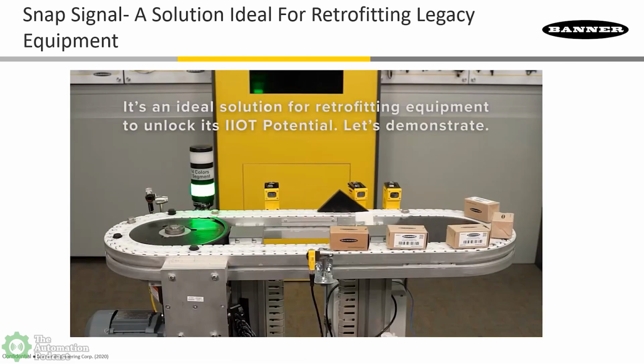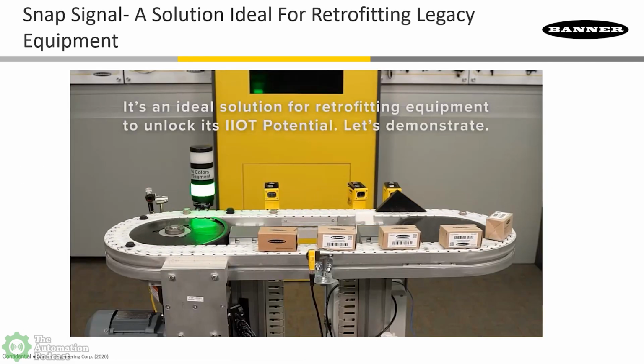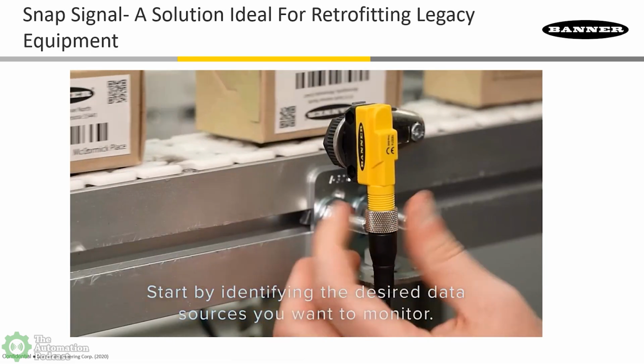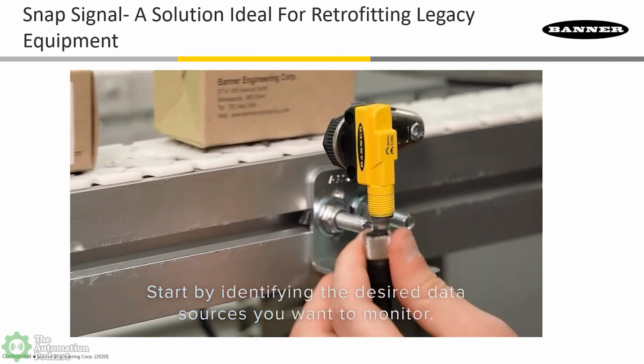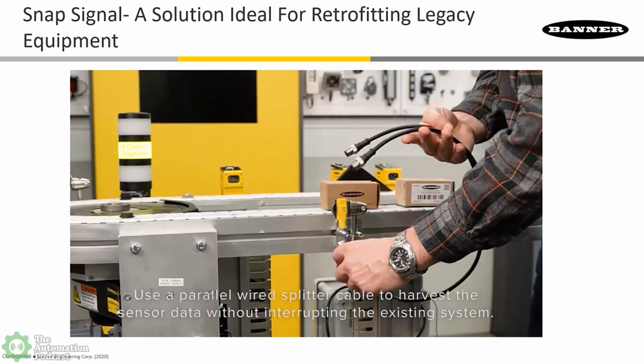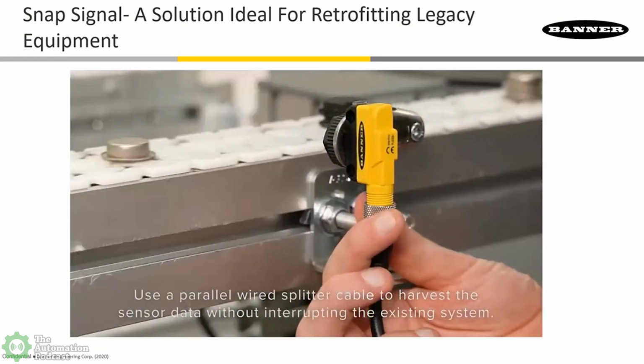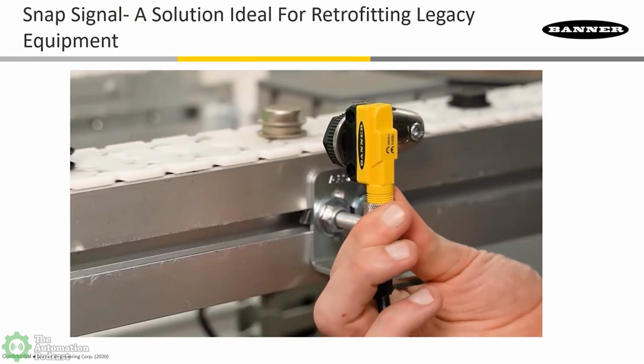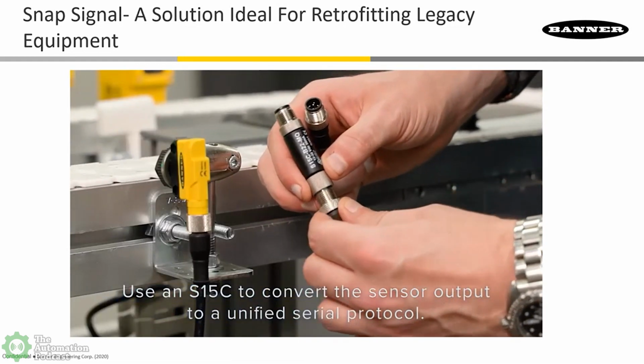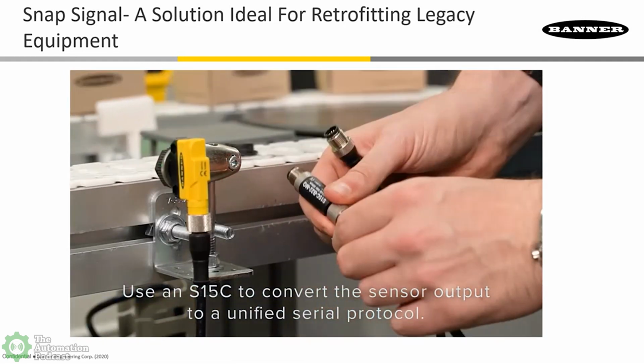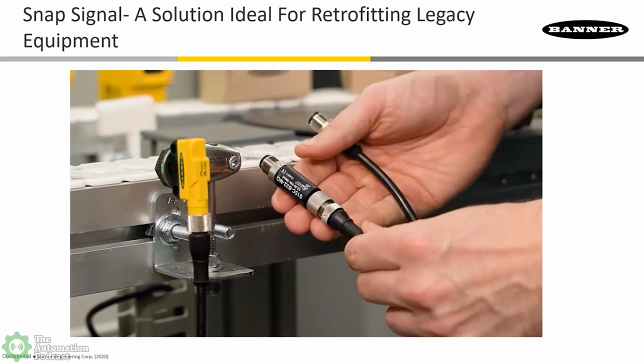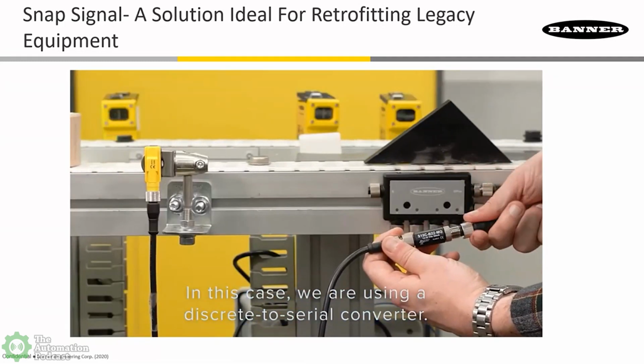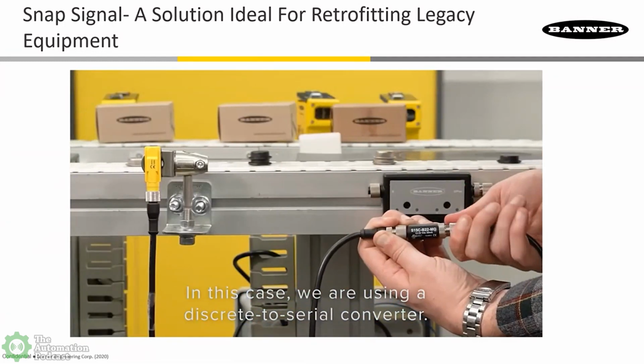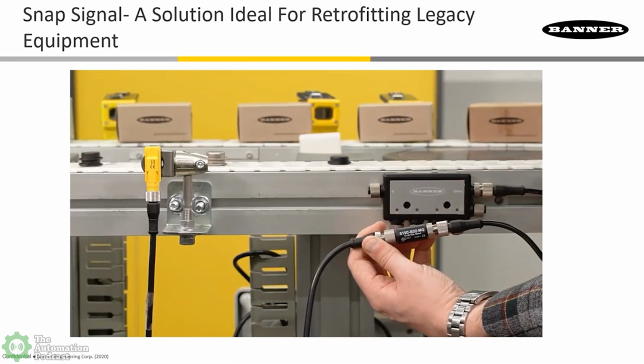Here's a quick video that highlights just how quick it is to harvest sensor data. We're going in there with a parallel wired splitter, plugging it into the sensor that was already installed. One branch goes back to your PLC, and one goes back to the small S15C converter that takes in that discrete sensor and converts it over to that unified serial protocol. And here we're just plugging it into a...